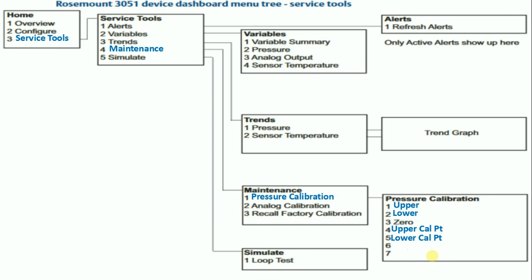For knowing the limits of the pressure or differential pressure transmitter, we can check the lower sensor limit and upper sensor limit, so we cannot set the range above this limit, especially with foundation fieldbus.